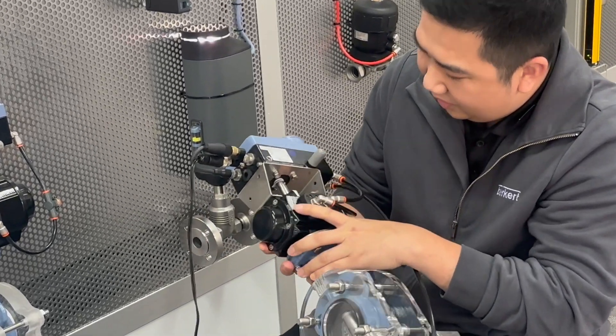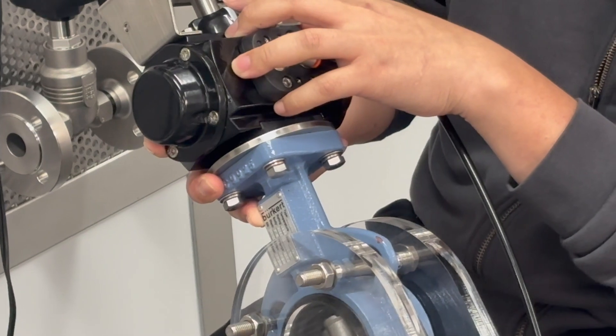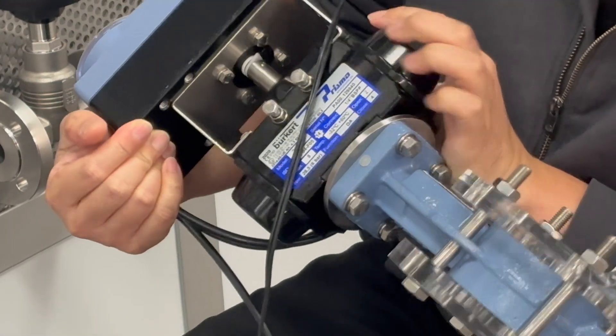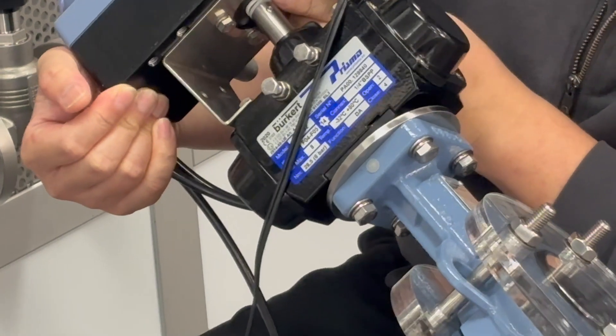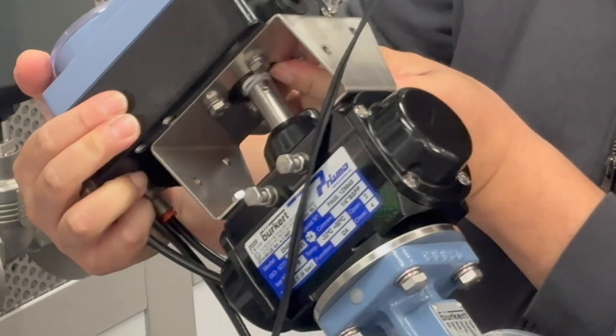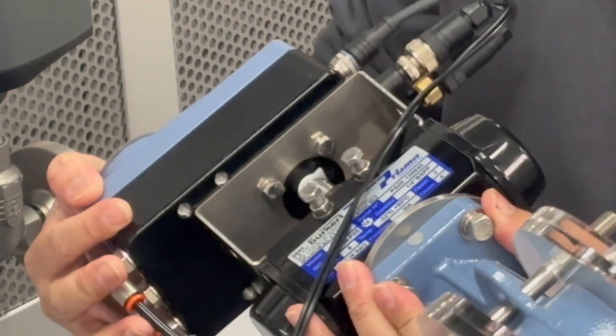As you can see here, a common problem is that when they're assembled on third party rotary actuators, the tension on there is not actually fitted correctly. Here you can see there's an arrow, and it's got to be between the two points that's marked on the actual unit itself, down here.